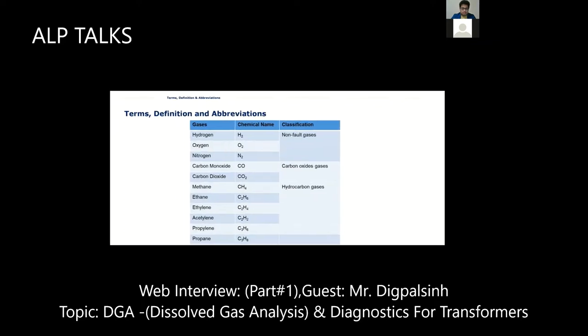First, hydrogen. Hydrogen is a stray gas. You always find hydrogen. Even if some fault is not there, when you use a transformer for 3 to 4 years, 5 to 6 years, some amount of hydrogen will come. That is fine for the transformer. Similarly, oxygen and nitrogen. Some amounts of oxygen and nitrogen you always find in the transformer oil.